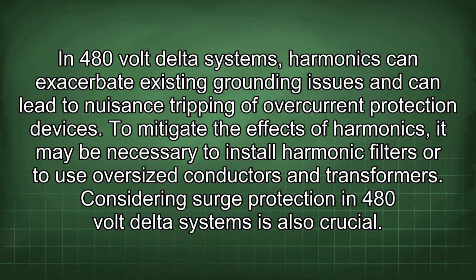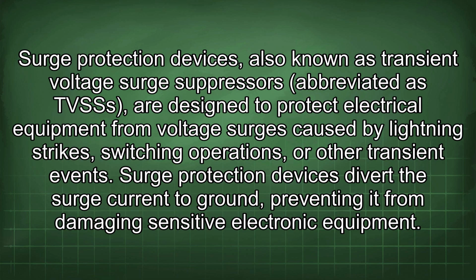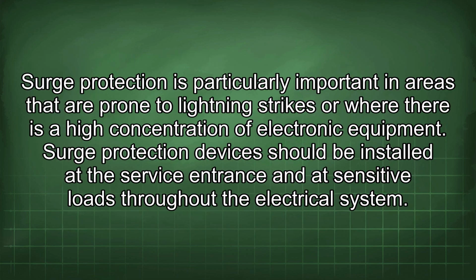Considering surge protection in 480-volt delta systems is also crucial. Surge protection devices, also known as transient voltage surge suppressors, abbreviated as TVSSs, are designed to protect electrical equipment from voltage surges caused by lightning strikes, switching operations, or other transient events. Surge protection devices divert the surge current to ground, preventing it from damaging sensitive electronic equipment. Surge protection is particularly important in areas that are prone to lightning strikes or where there is a high concentration of electronic equipment.